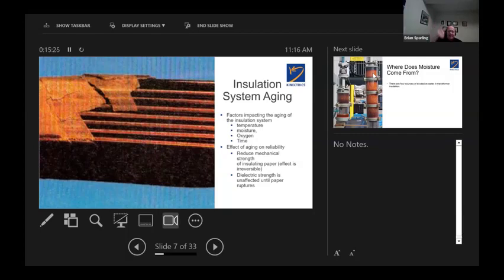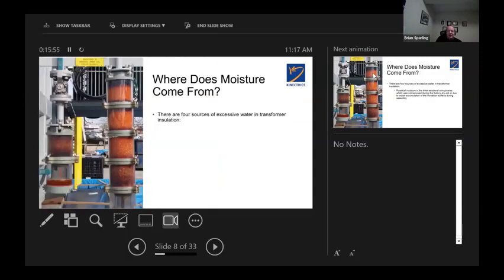It did not get reflected in the winding temperature simulator because it can't. And it was not really reflected in the oil temperature because it was of such a large volume of oil. But you can see what the impact was. The short circuit and the ripping and the tearing of the paper, which has lost all of its mechanical strength. And you can see how the conductors have separated themselves due to the short circuit impact on that transformer. That's why we're concerned about moisture. It's a major aging factor.